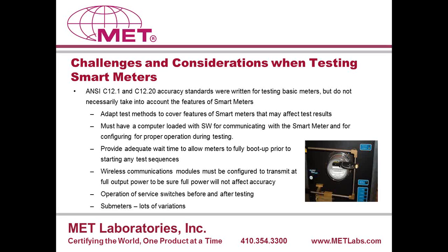So some of the challenges when testing smart meters: the standards, for the most part, were not really written for the smart meters as we see today. That's changing. Of course, ANSI committees and working groups are constantly working toward keeping up with technology and those evolutions, but that takes time. And so we've got the standards here as they're written today, C12.1 and C12.20, and we have to take into account things like the wireless modules. Are we going to transmit at full power to make sure that that isn't going to affect accuracy?